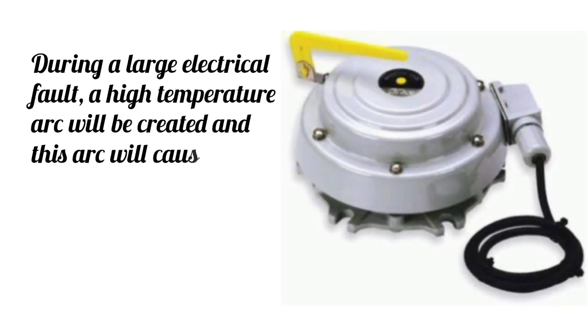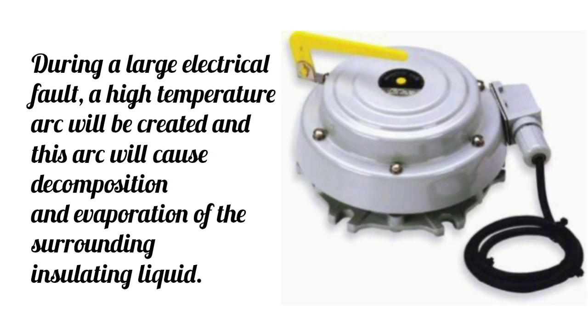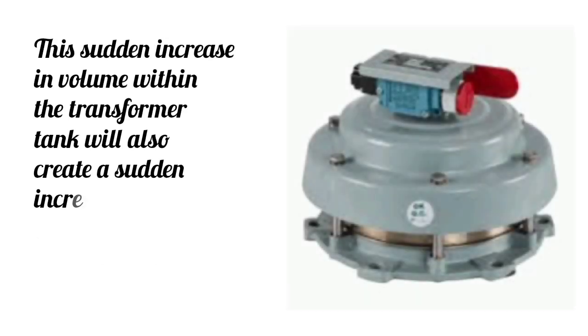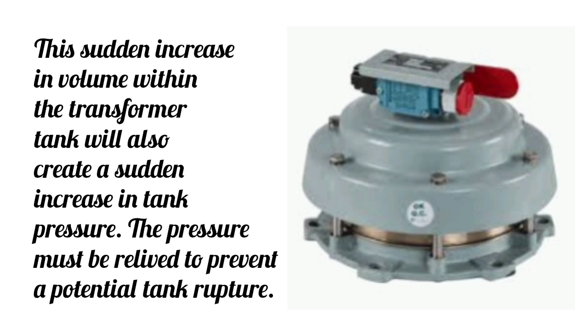During a large electrical fault, a high-temperature arc will be created and this arc will cause decomposition and evaporation of the surrounding insulating liquid. This sudden increase in volume within the transformer tank will also create a sudden increase in tank pressure. The pressure must be relieved to prevent a potential tank rupture.